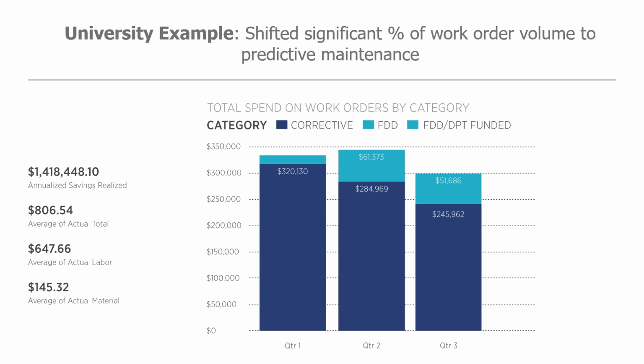So just to drive that home a little bit, if we think about a typical hot call, let's say we go out, we look at the thermostat, we try to figure out where the problem is. We might get an additional call and go back and actually get into the ceiling and see what's going on. But we think about the investigation time it takes to really find the root cause. Now, if we shift to a predictive process where we can plan that we know these 3 boxes are having consistent problems, we know that they're more important than the other 4 issues that are also happening on that floor, so we want to address it first.